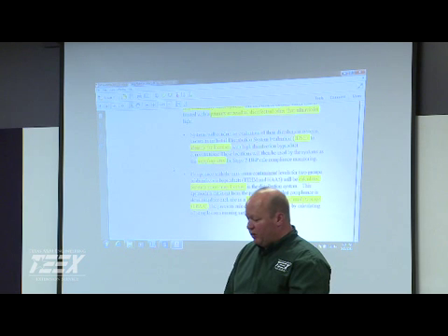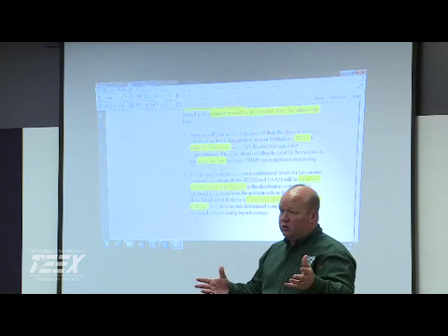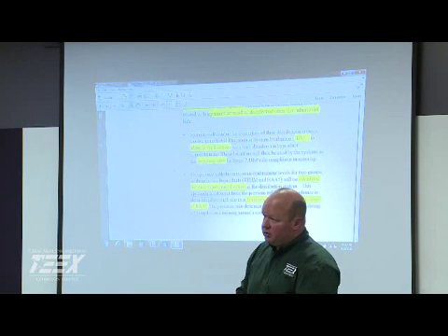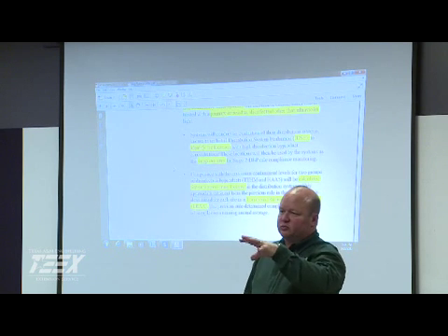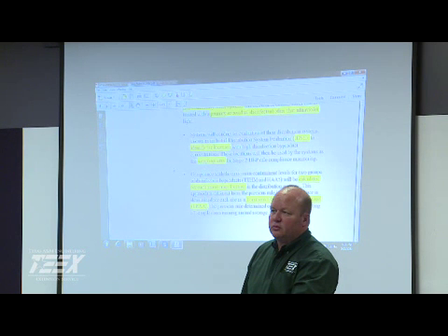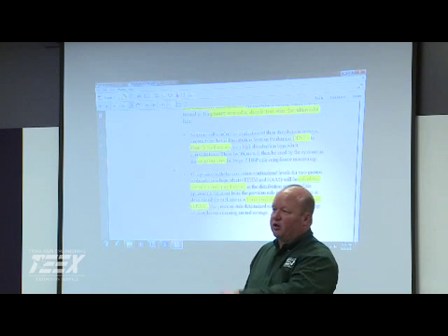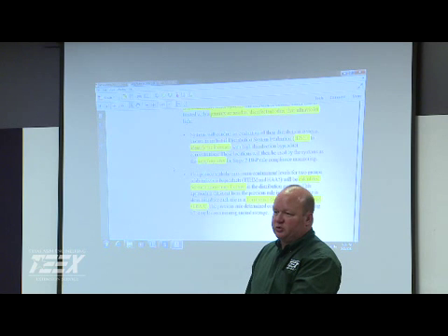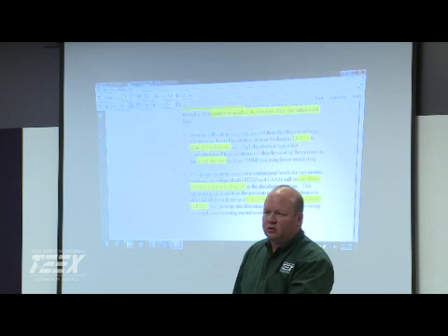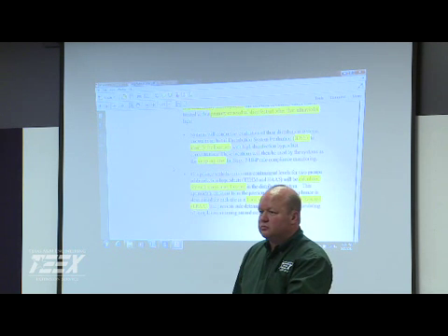Initial distribution system evaluations. When we start looking at our disinfection byproducts, we have to figure out where our hotspots are in our system, and then we have to monitor those regularly. So how many did y'all pull in y'all's system when you first started to evaluate it? Probably about 8. Yeah, I think 8 different sample sites. And then you had to build a profile over them for a period of time and determine which ones you were going to use. And how many are you pulling now? We're still pulling four. We start, I think it's the last quarter of this year, and the rest of our systems will start Stage 2 monitoring in the 4th quarter of this year.